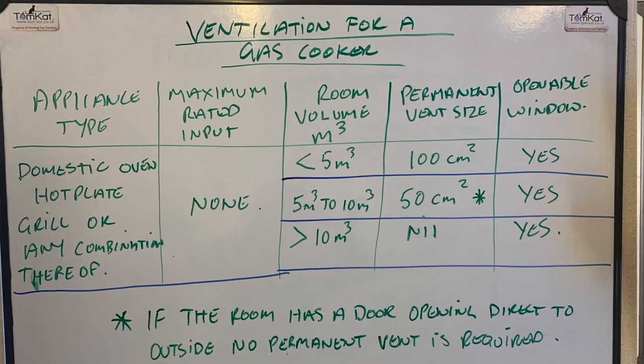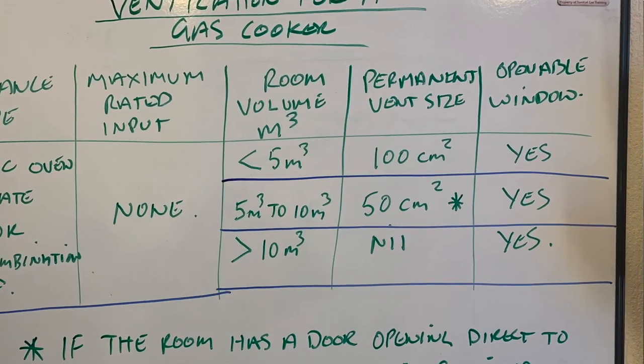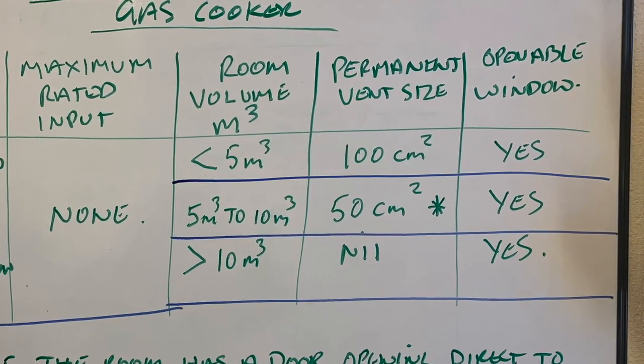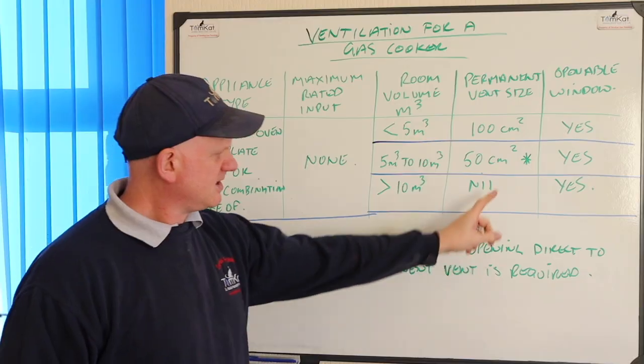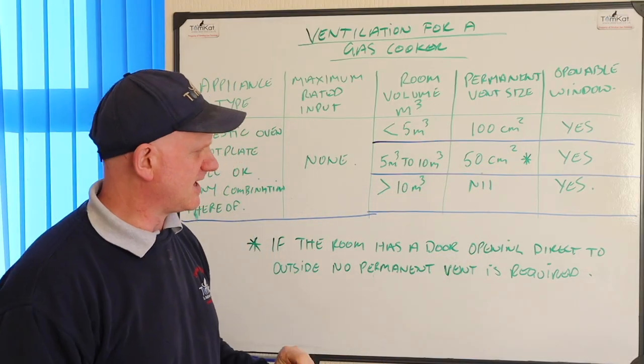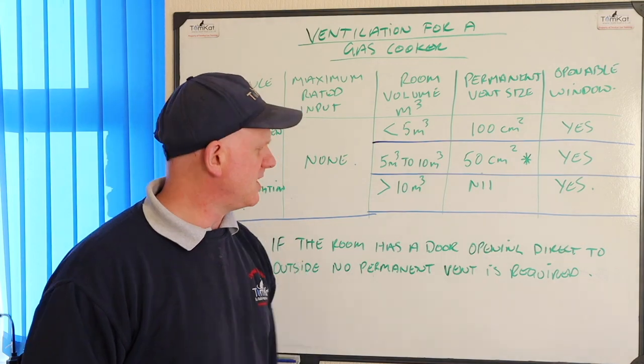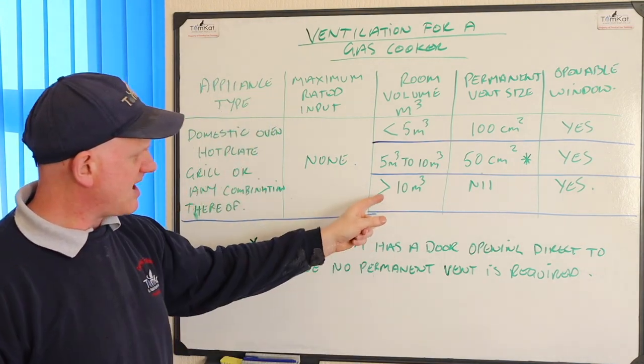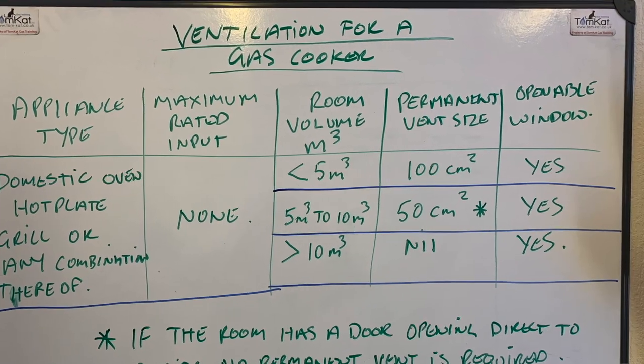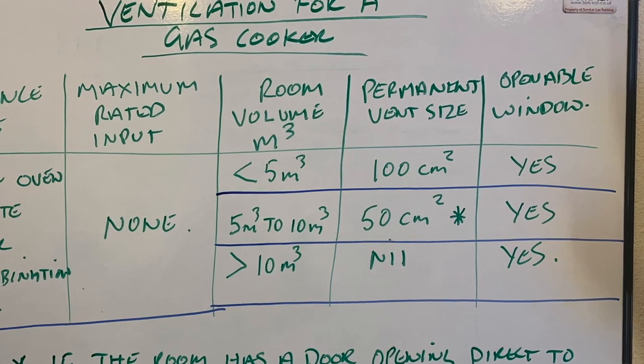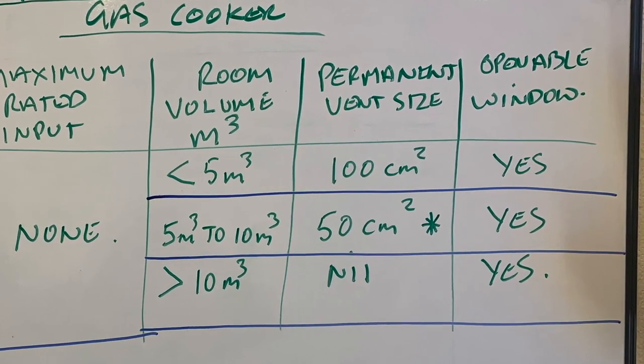If we have a room volume between five and ten metres cubed we need 50 centimetres squared — there's an asterisk we'll look at in a moment — and we also need an openable window. If the room is greater than ten metres cubed, we don't need any permanent ventilation but we still need the openable window.